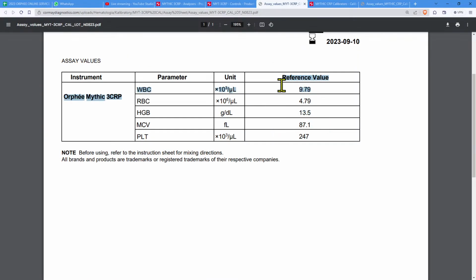What you need to keep in mind is the units that are used by you, where you can make a mistake, on the hemoglobin. If you use grams per liter, this will be 135 instead of 13.5, right? So the error can be made here. Keep this in mind. For the concentration of the white blood cells, red blood cells, MCV, PLT, it doesn't matter if this is to the power 9 or power 3, because this number will be the same.